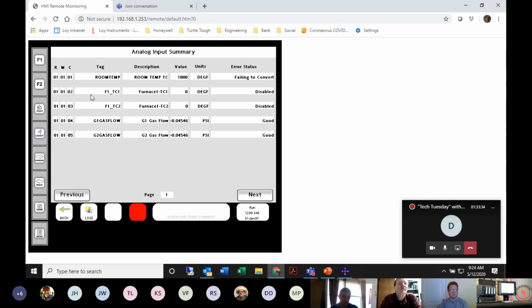I can click on this button, and that'll give me a full display here showing me rack 1, module 1, channel 1, the tag name associated with it, the description, the value. So this is the real-time value along with engineering units, and then it'll tell me if there's an error associated with it. It'll do this for all the analog inputs as I program them in the HC900. So as I program them, it just adds them to the list and allows you very quick access.